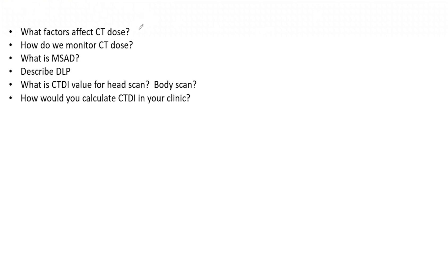So what factors affect the CT dose? The tube potential is a big one. Our dose for CT is proportional to KVP squared, so important to keep that in mind. The exposure time is important because similarly dose here is proportional to MAS.